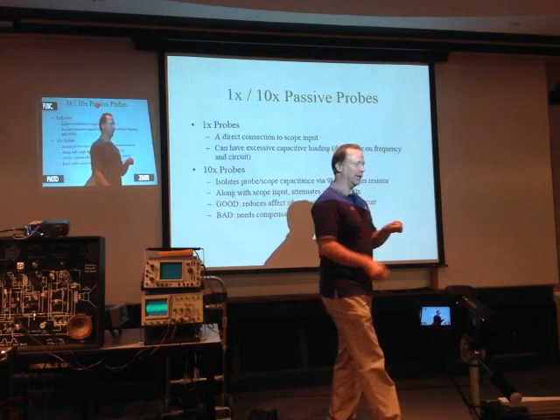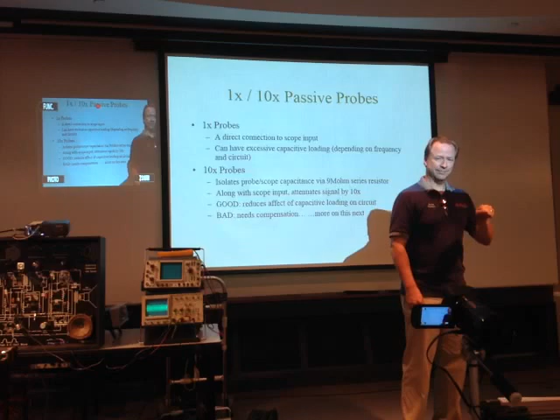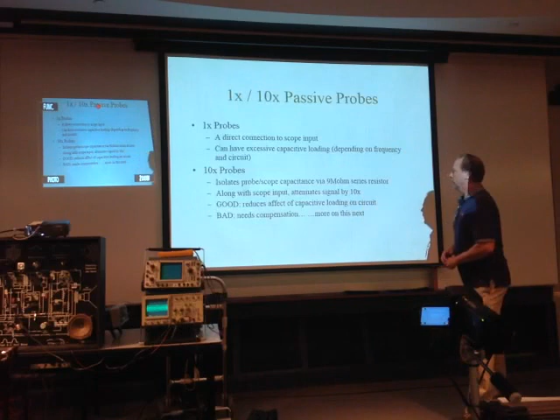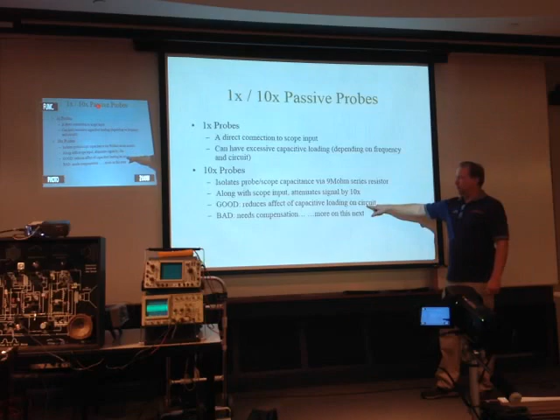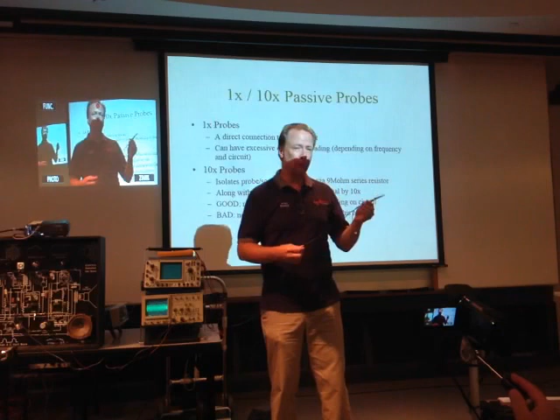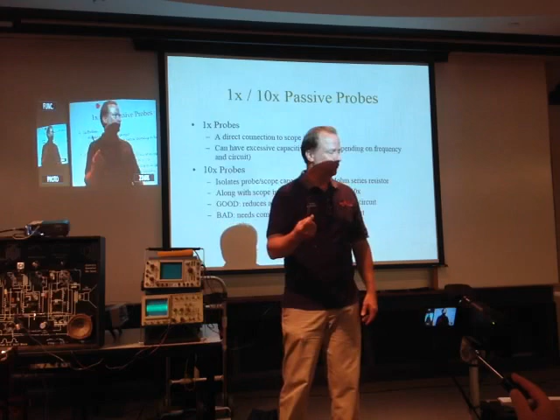So what it means is that the scale you set up on the scope, if I set it to 100 millivolts a division, and I connect up a 10x probe, it's now 1 volt per division. The scale is 10 times larger. It's not 10 times more sensitive. So again, along with the scope input, it attenuates the signal. Good thing, it dramatically reduces the effect of capacitive loading. These 10x probes might have an input capacitance of 10 or 15 picofarads. That can still be a lot on some of these tuned circuits, as we'll see in a moment, but it's a whole lot less than the 100 picofarads you have with the 1x probes.